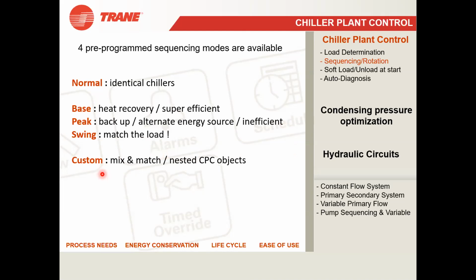So what is custom mode? Custom means, for example, a customer says they have 4 chillers of similar efficiency, but want every chiller to run only 250 hours in 6 months or 3 months, just a hypothetical example. So what happens is the CPC will mix and match the 4 chillers, running each one in such a way that after a stipulated time frame, every chiller runs an equal amount of time. It shouldn't happen that one chiller runs only 50 hours while another runs 250 hours and another 150 hours. The CPC synchronizes all the chillers, switching them on and off so that every chiller runs the equal time suggested by the customer or consultant. This is called custom mode.